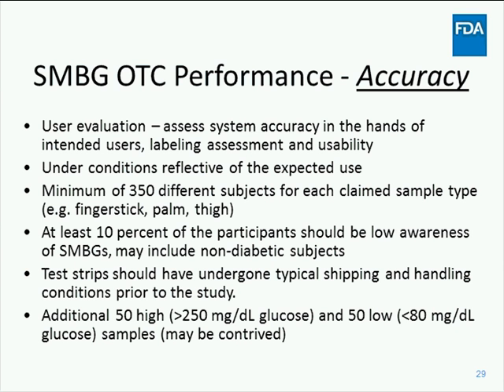As in the BGMS guidance, this document recommends that accuracy of the system be demonstrated in the hands of the intended user, which in this case is lay users. And this should be done under conditions reflective of expected use. The recommendation is to use a minimum of 350 patient samples obtained and tested by the lay users when they are given only the device and the device labeling with no training, coaching, or prompting. 350 samples should be obtained per claim sample type, such as for fingerstick, palm, or thigh.